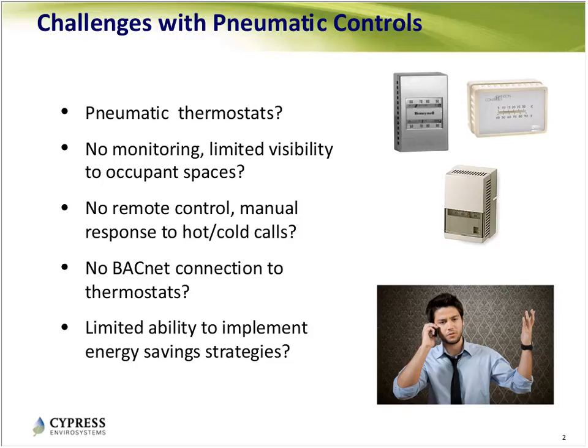Let me jump into what the problem is, what are these pneumatic controls. If you're on this webcast, you probably already have a good idea, but for those who don't, they look like the ones on the upper right-hand side of the slide. They're made by Honeywell, Johnson Controls, or Siemens, and they're pneumatic because when you turn the little knob to change the temperature, you hear a hissing sound - that's air pressure behind it. If you pull the thermostat off the wall, you'll find there are no wires, no batteries, no internet connection. It's all air pressure through little tubes that modulate the dampers, valves, and terminal units controlling heating and cooling.